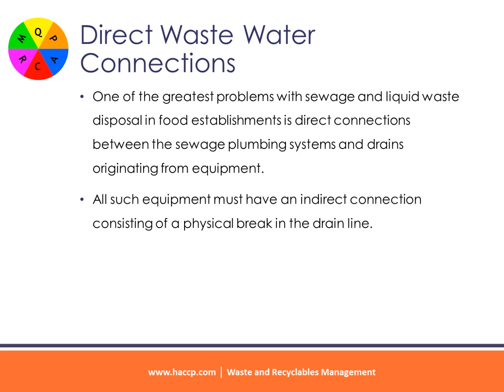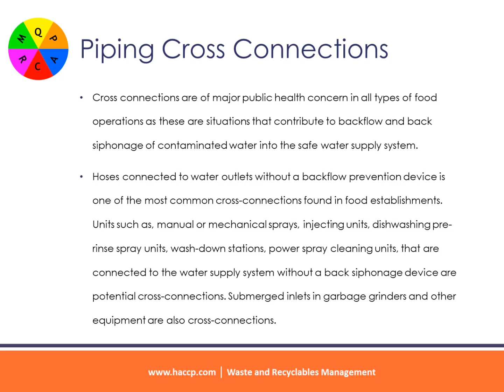Piping cross-connections. Cross-connections are of major public health concern in all types of food operations, as these are situations that contribute to backflow and backsiphonage of contaminated water to the safe water supply system. Hoses connected to water outlets without a backflow prevention device are one of the most common cross-connections found in food establishments. Units such as manual or mechanical sprays, injecting units, dishwashing pre-rinse spray units, washdown stations, and power spray cleaning units that are connected to the water supply system without a backsiphonage device are potential cross-connections. Submerged inlets in garbage grinders and other equipment are also cross-connections.